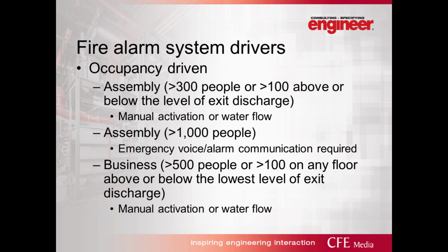Now, the one thing also that I wanted to mention early on is that almost all of the occupancies, manual activation utilizing manual fire alarm boxes is an option when the building is fully sprinkler protected. There are exceptions in the IBC as well as NFPA 101 to eliminate all but one manual fire alarm box. And one manual fire alarm box is required, and that's typically located in a staffed location. In a hotel, we would typically place that at the front desk. In an unstaffed building, where you don't have a 24-hour staffed location, it's typically located somewhere near the control equipment or annunciator panel. And the intent of that device is to be able to activate a whole building alarm should something be amiss, or also to notify first responders off site.